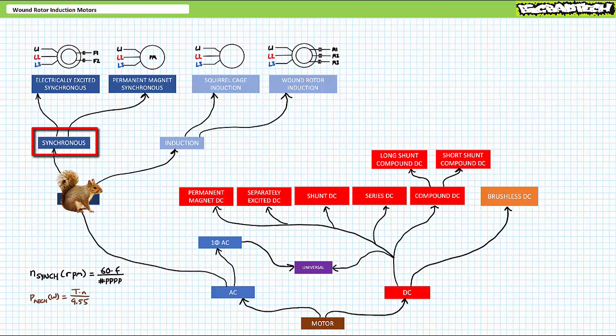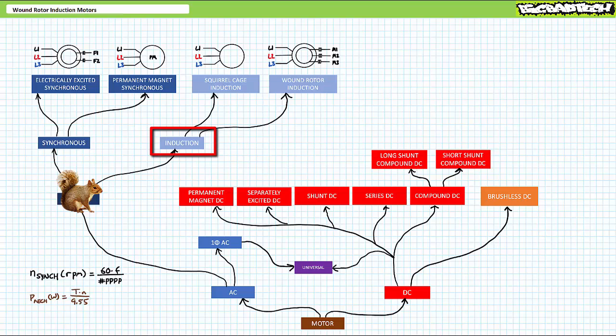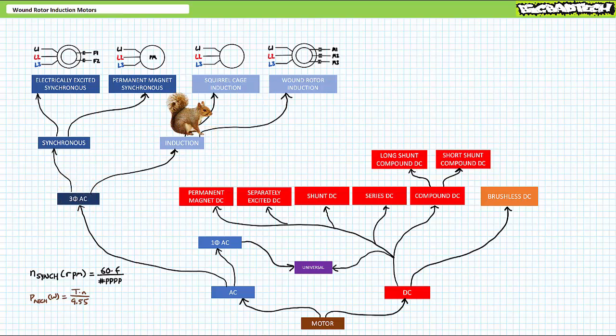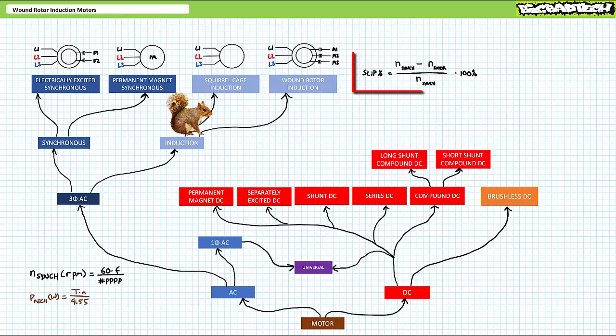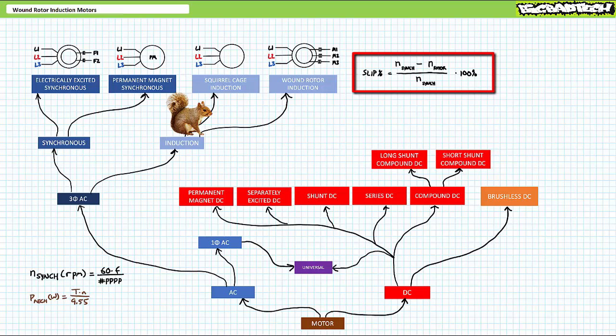Within their operational range, synchronous motors are fixed speed motors, whereas we might expect the rotor speed of an induction motor to vary as a function of applied torque. Within the induction branch, there are two main types: squirrel cage induction motors and wound rotor induction motors, the topic of today's discussion. All members of the three-phase AC induction motor family make use of a rotating magnetic field in the stator, and the rotor speed varies as a function of applied torque, where the differential between the resulting rotor speed and the stator synchronous speed is known as slip, often expressed as a percentage using the formula: synchronous speed minus rotor speed, divided by synchronous speed, times 100%. Both squirrel cage induction motors and wound rotor induction motors exhibit this behavior.